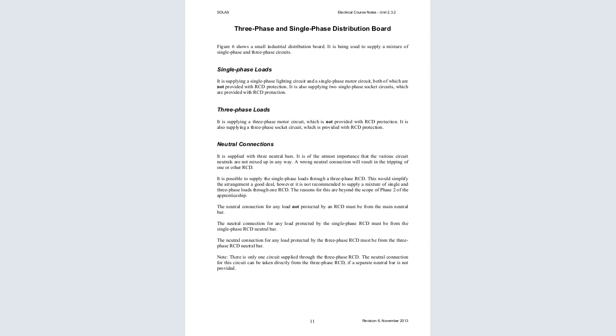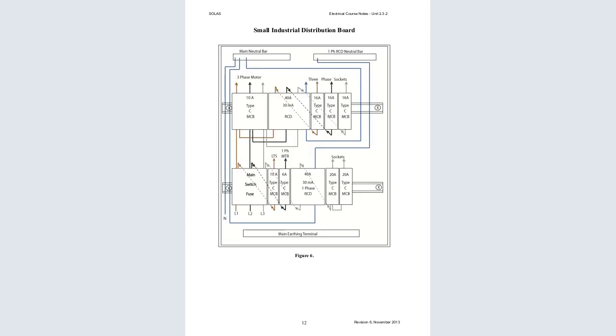Note that there is only one circuit supplied through the 3-phase RCD, and the neutral connection for this circuit can be taken directly from the 3-phase RCD if a separate neutral bar is not provided. We have a small industrial distribution board. We have the main neutral bar. We have a single phase here. The main earthing terminal is here.